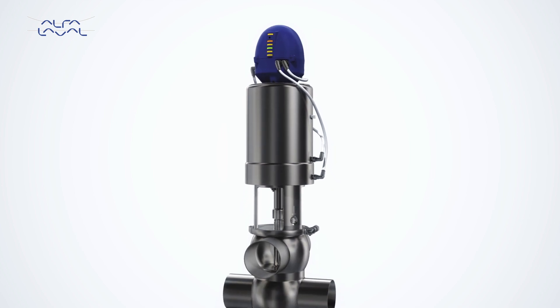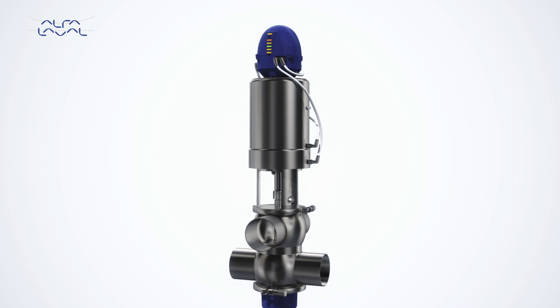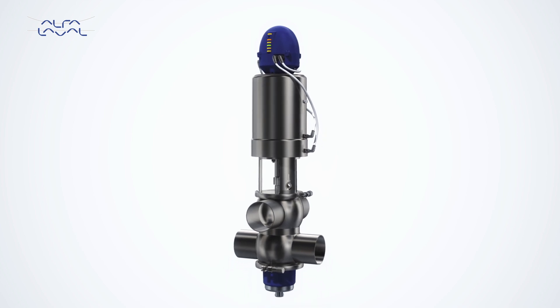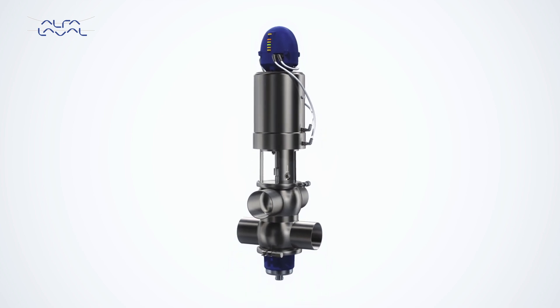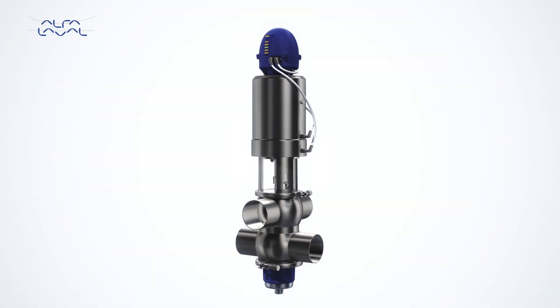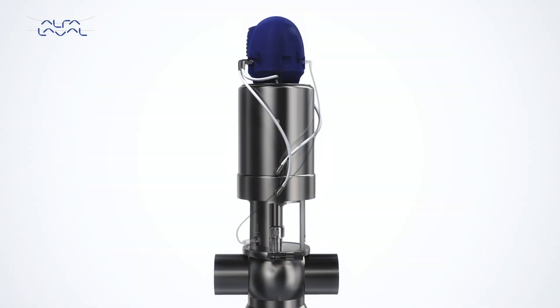The Alfa Laval unique mix-proof CP3 valve can be fitted with any level of sensing and control. To enable verification of the upper seat lift, an external proximity switch can be added. To comply with 3A PMO, the external proximity switch is required.